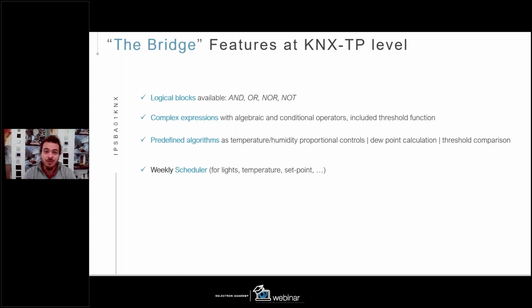I said we will also have a scheduler. This is because the bridge can receive the date and time from KNX, or can connect over IP to an NTP server and send the date and time on KNX-TP to keep the date and time aligned on our KNX system. Thanks to that, we can also enable up to 16 weekly schedulers inside the device, which means that we can enable static timers from ETS. And we will also have up to 8 different virtual holiday applications.